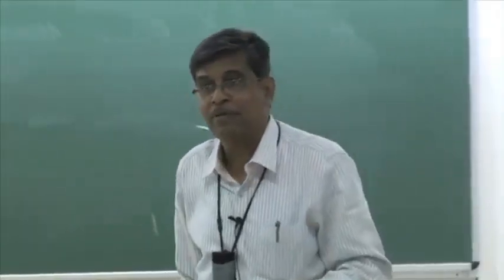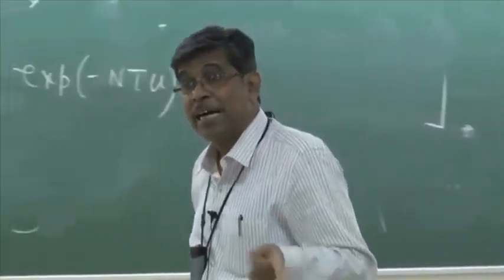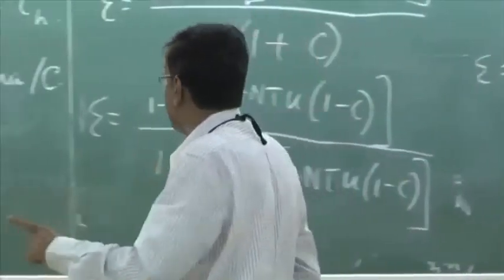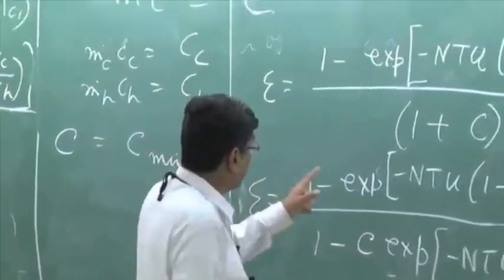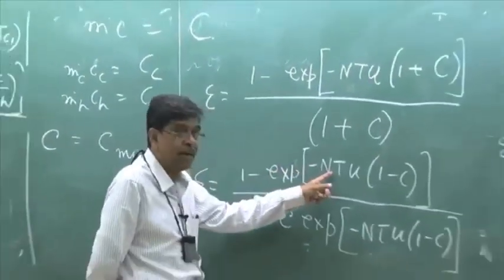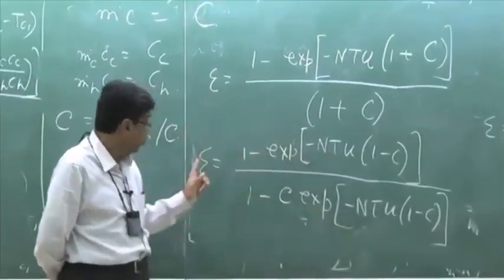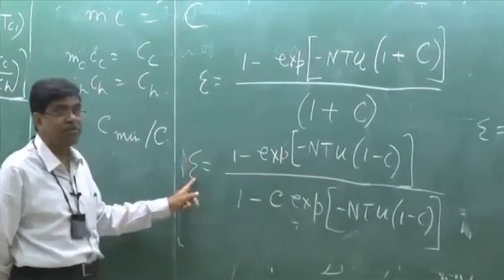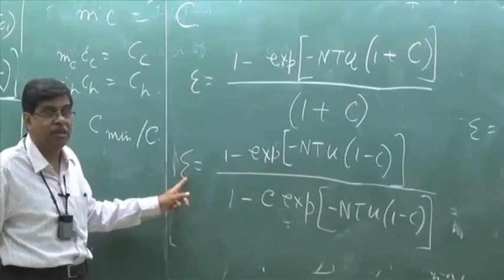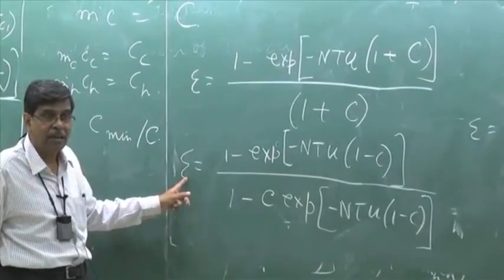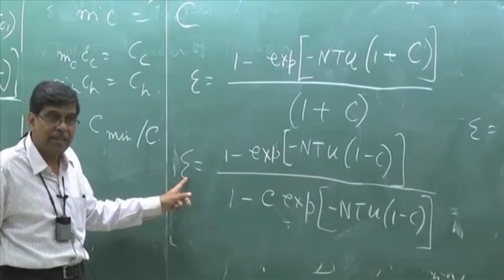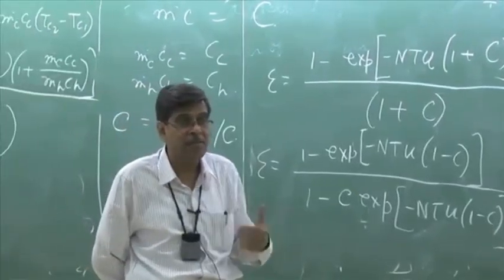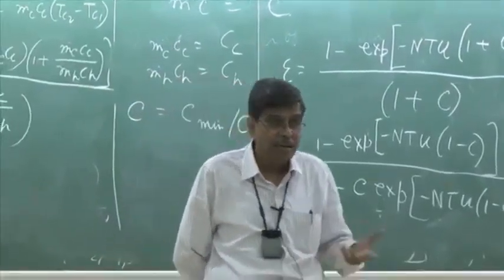Where the temperatures are given and sizing is to be made, LMTD is useful because finding NTU as a function of epsilon would be difficult. So where rating and heat load are not given but size is given, the NTU-epsilon method is an explicit method to find out effectiveness, from which temperatures are found. LMTD is useful when temperatures are given and sizing calculations are needed.